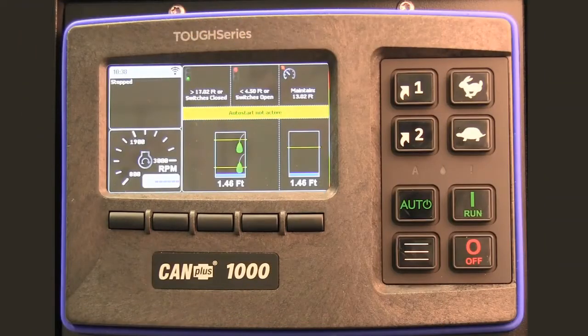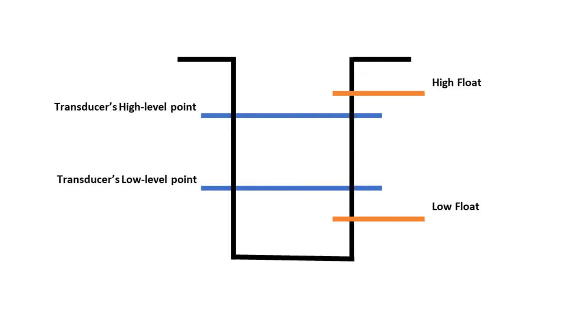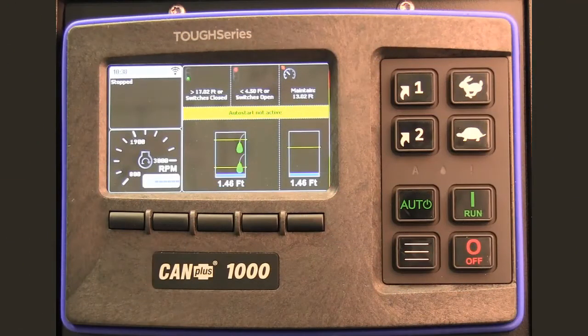To ensure the start and stop events come first from the transducer, the switches must be configured as shown, such that the high switch opens and closes at a level above the transducer's high level point, and the low switch opens and closes at a level below the transducer's low level point. The following simulation will show the dashboard's behavior under this configuration and scenario.